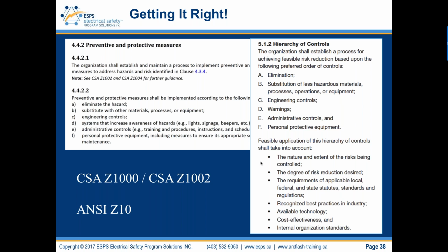and not cost prohibitive. Then we want to look at warning signs and barricading, or systems that increase awareness of the hazards: lights, signage, beepers, barricading. So you need to use an electrical work zone for energized electrical work with red danger tape, tagged, or some other means of barricading, which your electrical safety program should identify. The fifth item is administrative controls, training, and procedures. So we want to use training and procedures, and then again, there are gaps there. And then PPE is last.